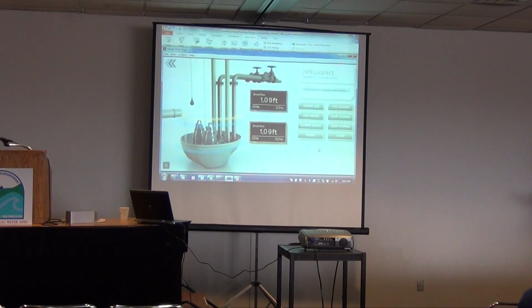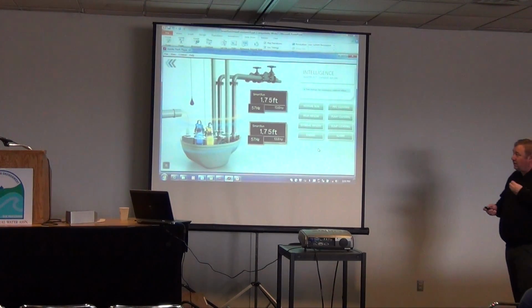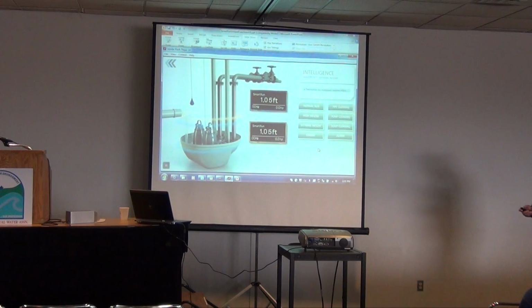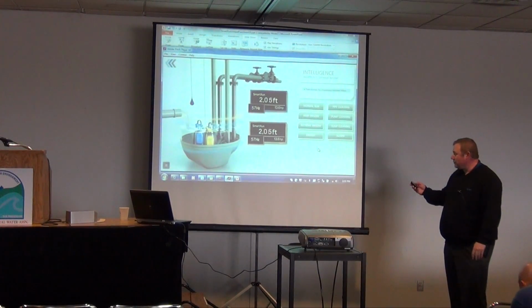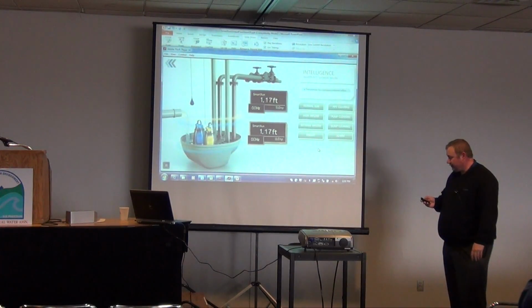They did a lot of tests with that to see how it would end up, and they did about a 45-day test, and it was uncanny that the pumps really had about the same runtime over that period of time. The key to that is it helps keep costs down and keeps components less within the panel. For me, being an operator at one time in my life, it's a lot different than what I was used to, but it's a unique development in pumping wastewater and helping with energy savings.